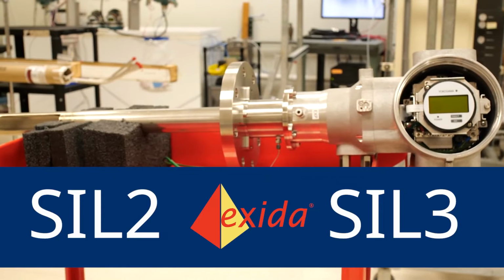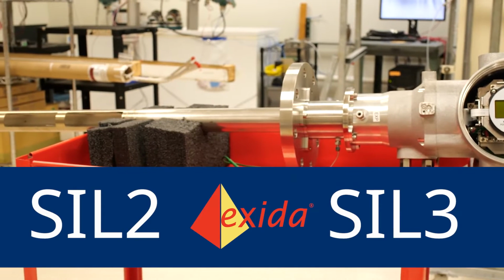The TDLS8200 needs not only to be reliable but also safe, robust, and easy to install. By designing the TDLS8200 to meet SIL for functional safety and certifying it for many regional explosion-proof, flame-proof standards, we've created a product that can be used in safety systems across the globe. Even the alignment mechanism, which functions internally, can be adjusted while still maintaining an explosion-proof structure. We've done our best to integrate the best solutions into the TDLS8200.